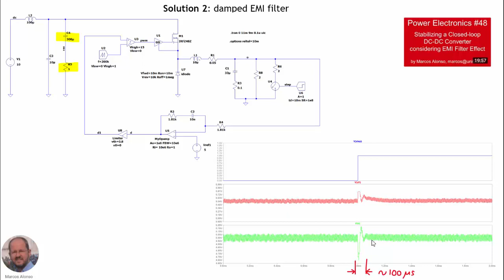So again, we are going to study this from the point of view of the impedances of the filter and the converter. In this case of the damped EMI filter, we have this diagram for the filter, so we can obtain also the impedance Zf as shown here using this expression. And also we have seen that in the design of the filter, this is the condition that we need, because we need that the impedance of this capacitor here, Cf1, must be much lower than the series resistance Rf at the resonant frequency of the filter.